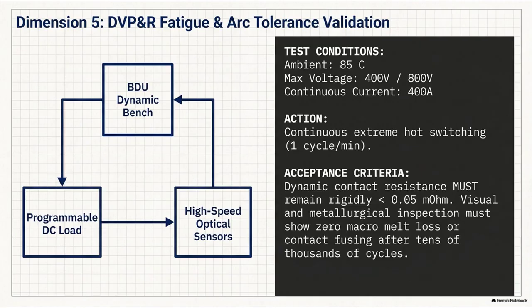Correct. But they also perform a highly sensitive check for what engineers call sticky friction. Sticky friction. Yeah. They apply tiny, very precise, low-voltage test currents through the main high-voltage system and then command the relay to open. They use the oscilloscopes to analyze the microsecond decay curve of that test current to ensure the internal mechanical springs rebound perfectly and aggressively.